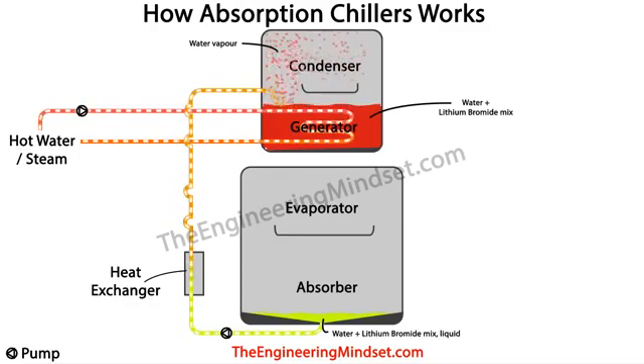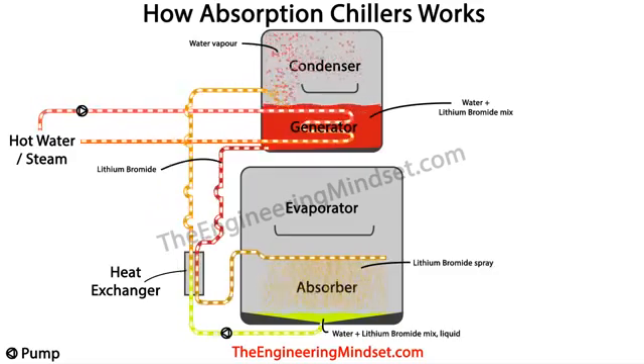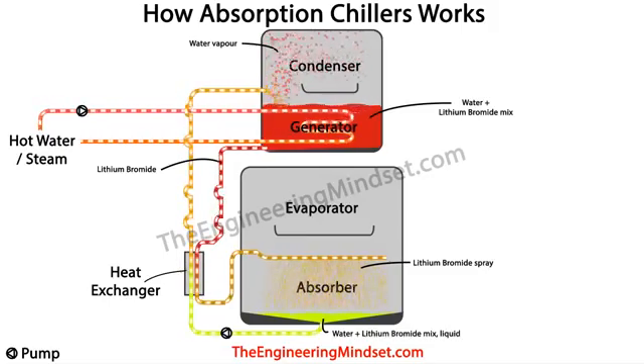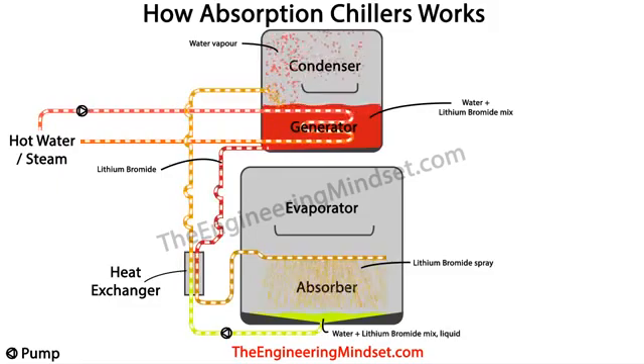The heat from this hot water or steam causes the lithium bromide and water to separate. All the water particles will start to boil off and will fill the condenser with a hot water vapor or steam. Then the heavy lithium bromide particles will sink to the bottom and form a concentrated liquid. This hot liquid flows down to the heat exchanger where it transfers its heat into the weak solution line, running in counterflow.